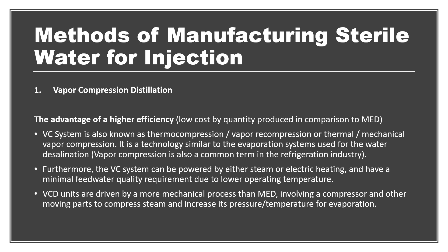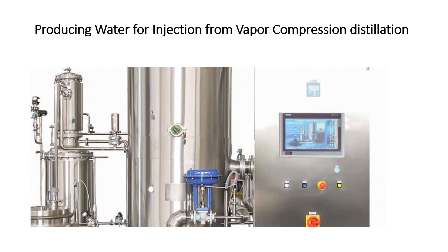The advantage of the vapor compression method is that it is used for commercial production, can produce thousands of liters at high speed, and has higher efficiency and lower cost compared to other methods. It is also referred to as thermal compression, vapor compression, thermal vapor compression, or mechanical vapor compression. The technology is similar to evaporation systems used for water desalination. The vapor compression system can be powered by either steam or electrical heating and has minimal feed water quality requirements.